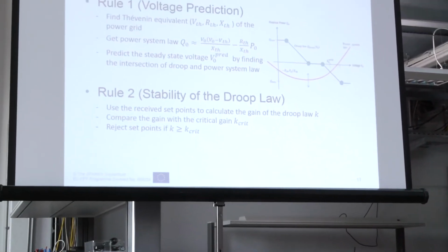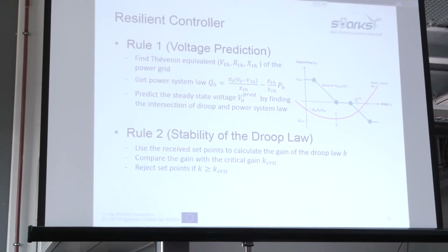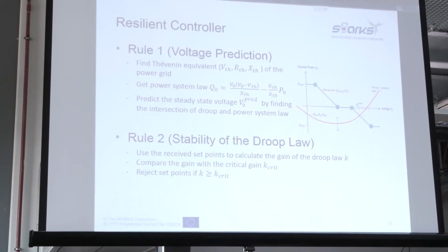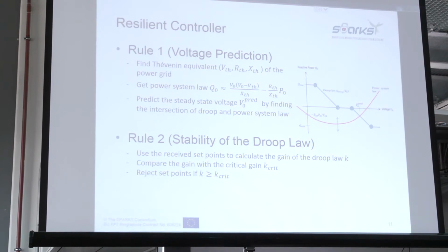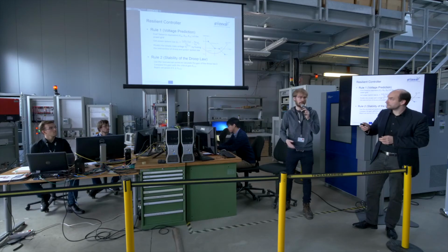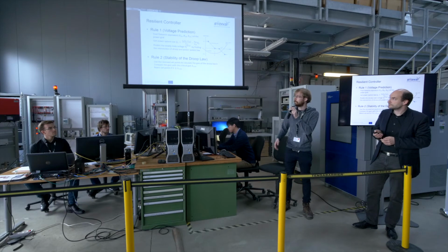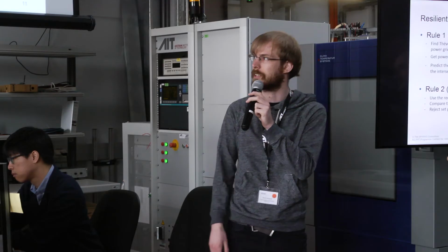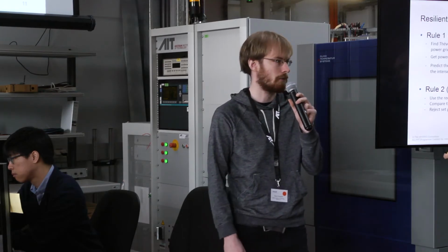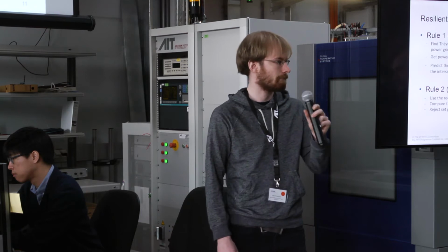But in today's demonstration, we focus on rule 2, the stability of the Droop law. We check the gain of the Droop law and compare it with a critical gain, beyond which it could start to oscillate under the conditions we just saw. We will show the distance between the actual gain and the critical gain. If this distance is positive, the system is okay; if it's negative, the actual gain K is greater than the critical gain, and the resilient controller would not accept the set points.